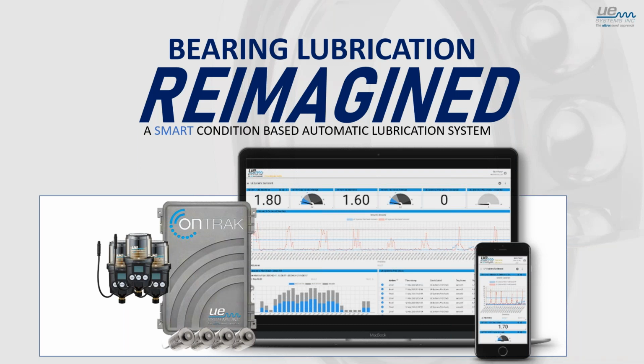We've done a lot of linear bearings too, with very short movements with a lot of success. What we have to do is change the way it collects data and how often it collects data. So it's not round robin, but done on a set interval. Once it sees movement, it takes more repeated data after that. It's something we're experimenting with to find the best approach, but we've had a lot of success with linear bearings and bearings that don't go all the way around.